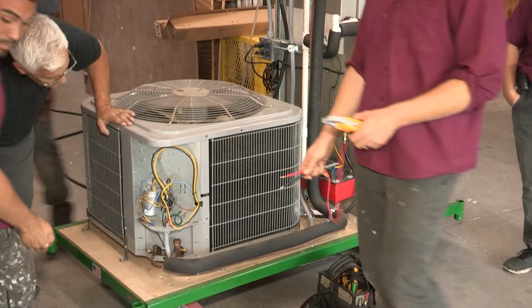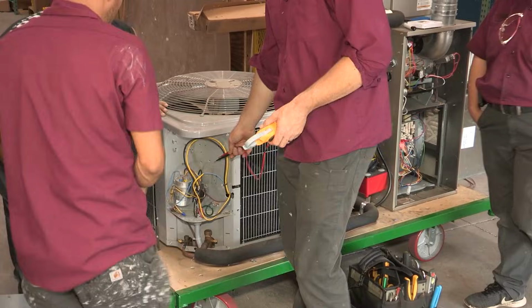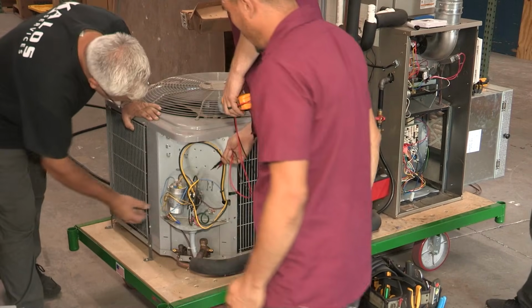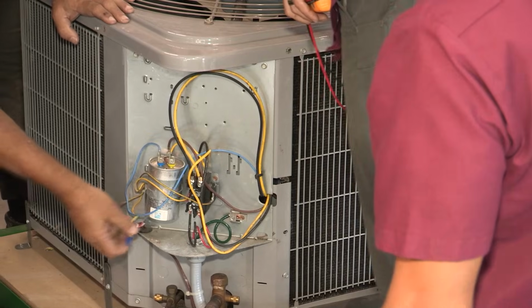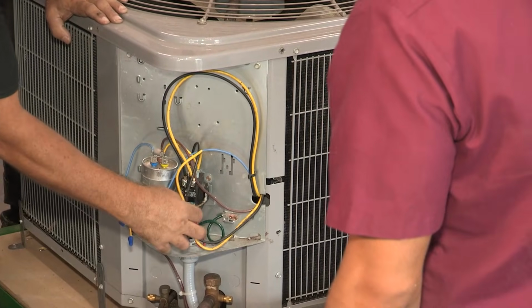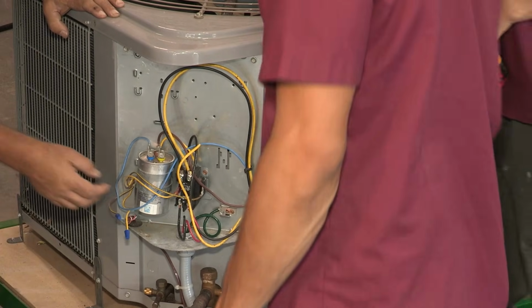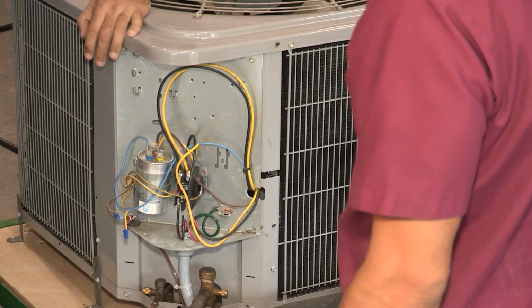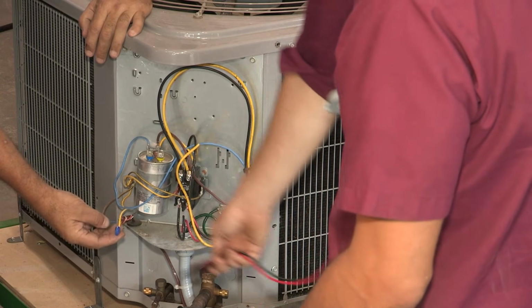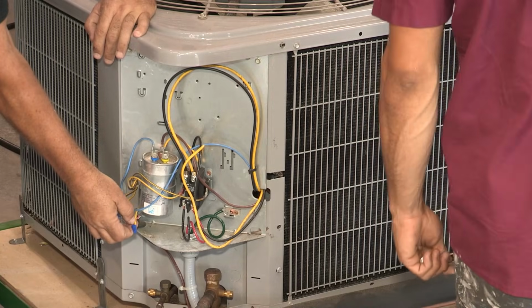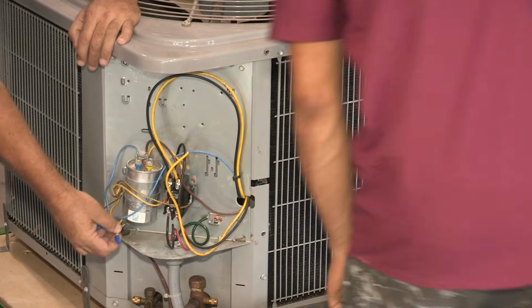So this is a straight cool, we don't have a defrost board to worry about. Do we have low voltage switches or low pressure switches? Looks like we don't. So our path goes straight to here, we still have power, and then we have our low voltage wire running down along here and back to our board. So it could be anywhere in there, right?